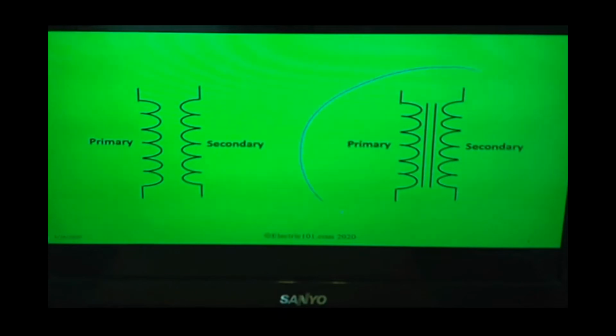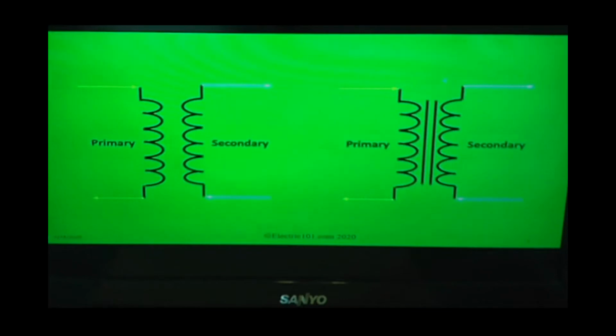Now this is only showing one phase of that transformer. This is a single phase transformer. That's all that is. Now how the transformer is going to work is simple. On the primary side, as power goes in, that power passes through the coils. That power creates a magnetic field that induces a voltage on the secondary, and that voltage on the secondary flows in the opposite direction.